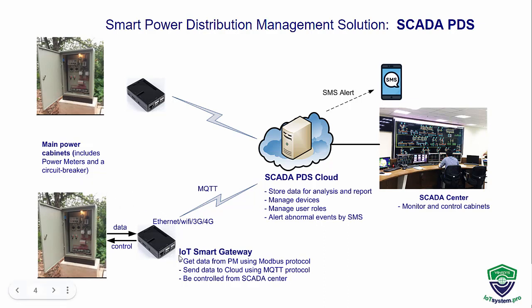Then we created an IoT smart gateway. This gateway gets data from the PMs using the Modbus protocol, then sends data to the cloud using the MQTT protocol. And this gateway can be controlled from the SCADA center by operators.